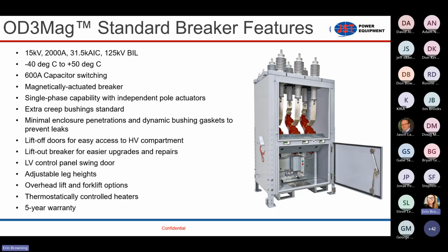You'll notice that on the enclosure itself, there's very few penetrations from a structural standpoint. There's not really many bolts that you can see that keep the breaker together. That was very intentional to help eliminate rust spots, but also eliminate and mitigate moisture ingress and sand ingress. I'll go into details on how we accomplish that.